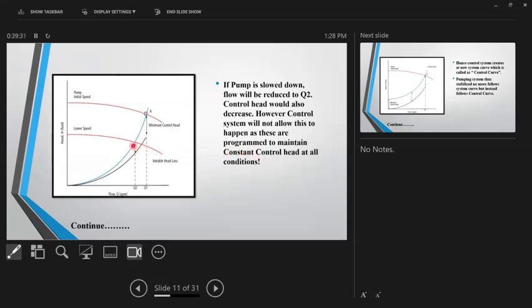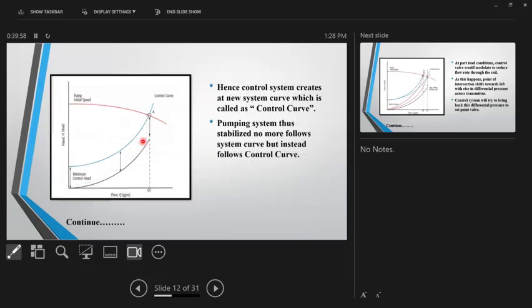Because of the simple reason that the control head is reducing, which should not happen. This can reduce, no problem. This is a variable loss, a function of flow. It can reduce or increase, no problem. The fixed loss cannot increase or decrease with respect to flow. So now we have a problem: what we feel logically should happen is not possible. So what happens to the system? What the control system does is create a new system curve. This was, let's say, your system curve, which started from 0. Now the control system somehow creates a curve which starts from some y abscissa, and then it continues like this.